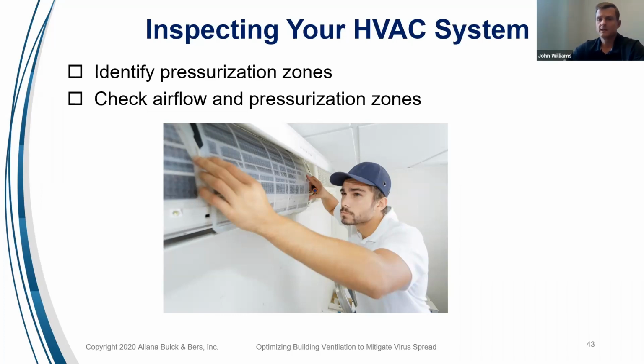If you don't have that, take a tissue and check your zone. Is the air being pulled into your room or is it pushing out of your room? Check your pressurization zones. That's a really good indication if your systems are working right or not.